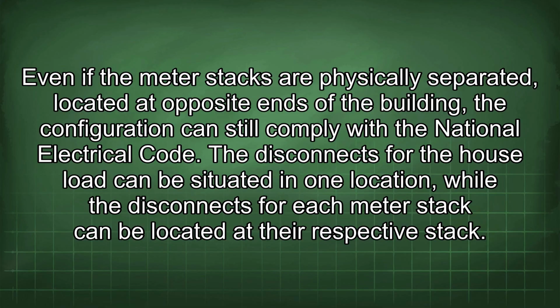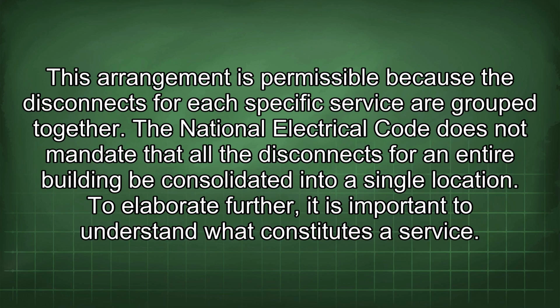The disconnects for the house load can be situated in one location, while the disconnects for each meter stack can be located at their respective stack. This arrangement is permissible because the disconnects for each specific service are grouped together. The National Electrical Code does not mandate that all the disconnects for an entire building be consolidated into a single location. To elaborate further, it is important to understand what constitutes a service.